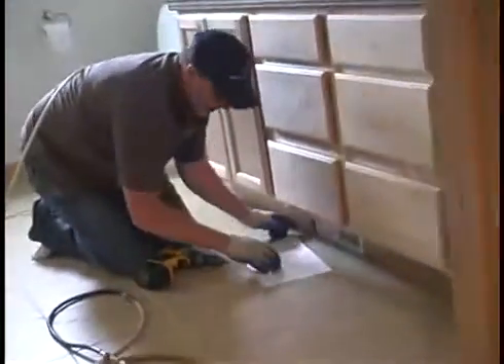And you see the pressure that this force has on it, it just pulls that paper right up to it. And then again, we're just agitating all the loose particles in there. Anything that's not already getting sucked up through the airstream is now getting pushed around through it. These skipper balls don't tear the inner liner, which a lot of brushes will do. These things will clean up to about a 10-inch air duct really well.